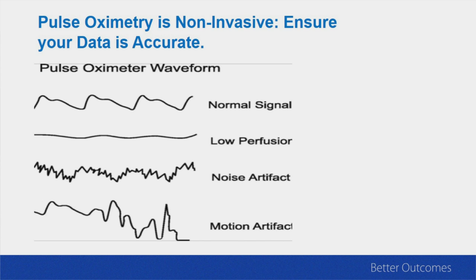There's also noise artifact. If you see how choppy that signal is, that can be caused by a couple of issues, and we'll talk about that. And then there's the motion artifact. With motion artifact, now we have movement that we're trying to look at, changing the size of your finger. We're trying to look at that blood coming into your finger or into that sensor site. And now the hand is also moving, or the head is also moving. Now we're getting serial wave movement going on that keeps us from getting an actual quality signal. So let's talk about what causes those abnormal waveforms. One of them is ambient light. When we have a pulse ox, it is looking at light that's traveling in a set wavelength.